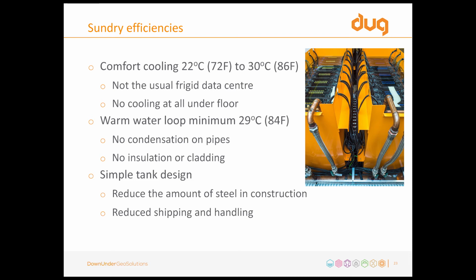Part of this is that we don't cool under the floor — we don't use the under-floor area for transporting air. If we did, we'd be cooling all the copper pipes from the power PDUs and the water pipes carrying water outside at 35 degrees. We want to keep as much energy as possible in that water, not pull it out through a draft. So under the floor stays around 35 to 36 degrees Celsius. This also means no condensation, so we don't have to lag cold water pipes or worry about all that. You won't get condensation at 35 degrees, which simplifies our tank design and more.